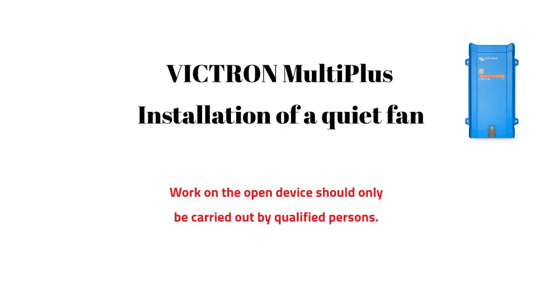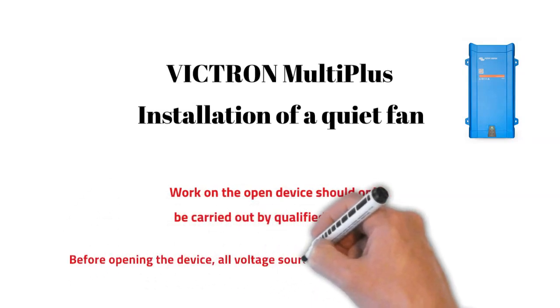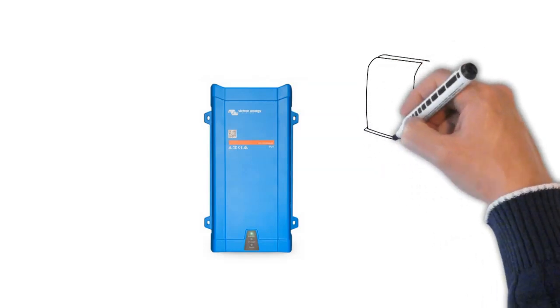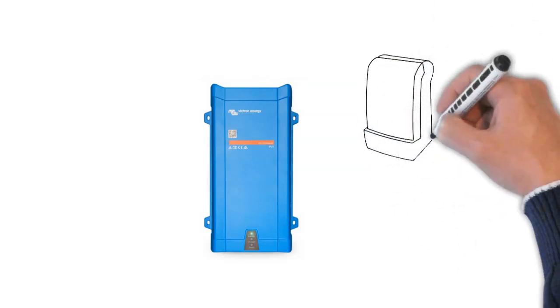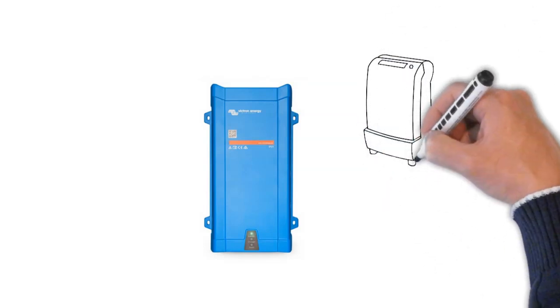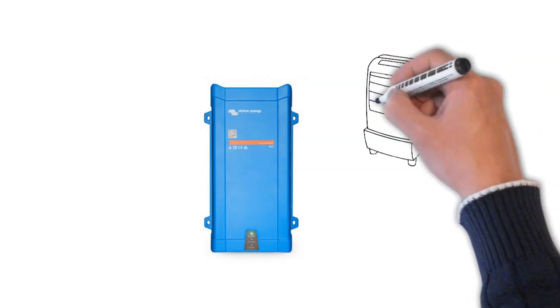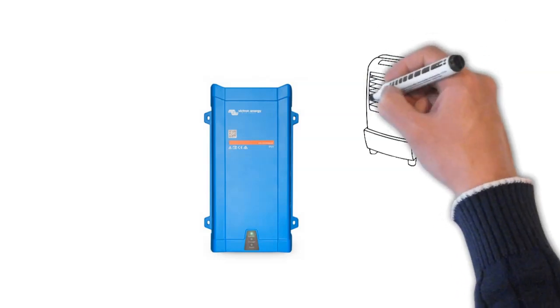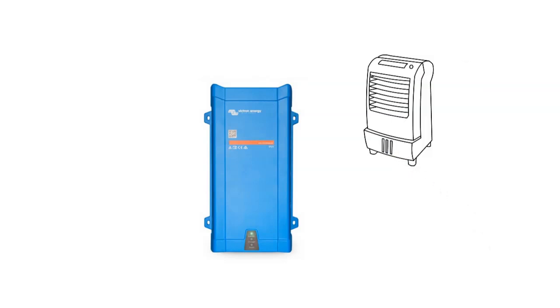Before opening the device, it is essential to remove all direct and alternating current voltage sources. Unfortunately, the integrated fan has its own resonance in the speed range, which is further amplified by the housing, resulting in a noticeable rotating noise when the fan is in operation. In order to replace the fan, the inverter must be opened.